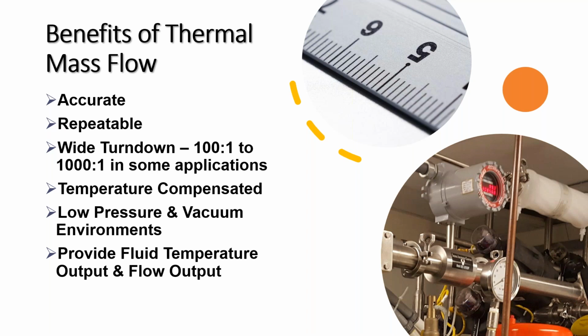And that goes back to some of our design, which we're going to get into in just a little bit. The other thing about thermal mass flow is it's very repeatable. Typically our units are plus or minus 0.2% repeatable back to the original calibration that you would be provided. So thermal mass is a very accurate and repeatable instrument that can be used for measuring gases or liquids.